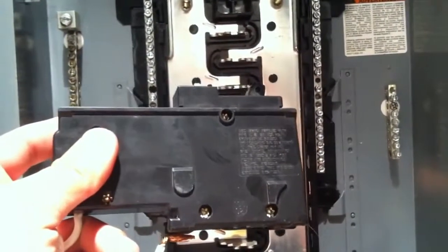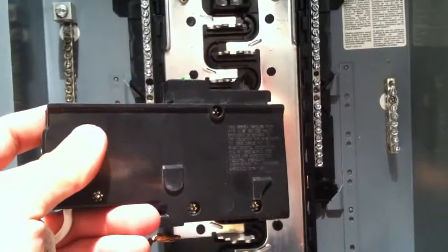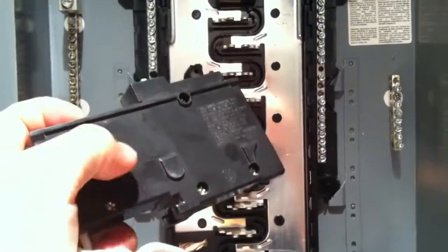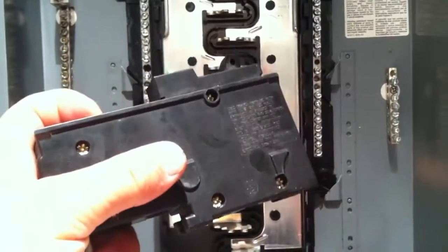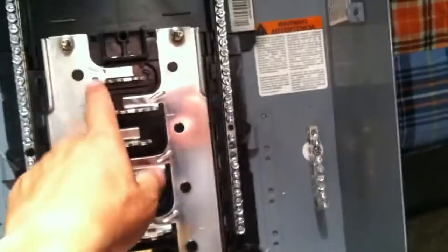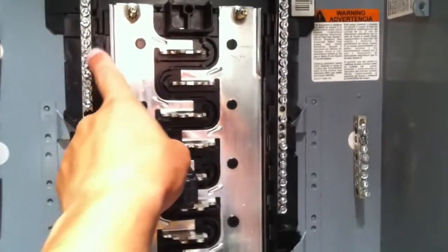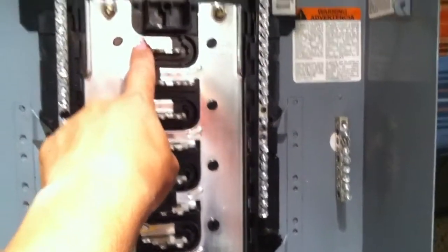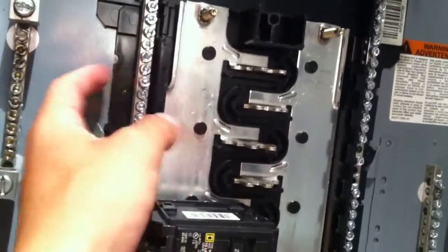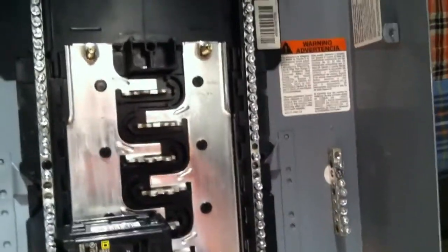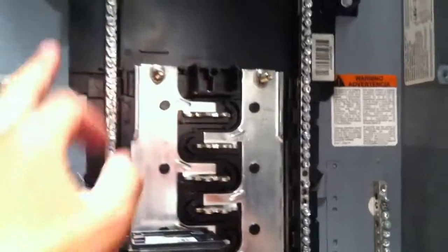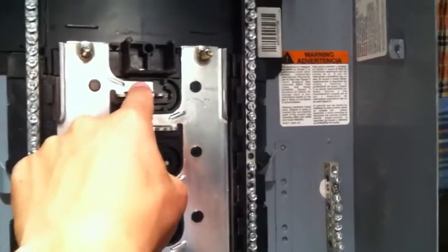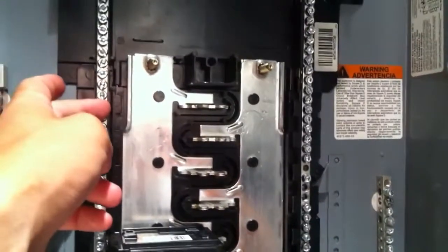So basically, to explain how these work in a little bit of detail, there's actually an electronic circuit in here. What it does is it monitors how much current is coming in from the hot line. Let's just say there's 15 amps coming in. It also monitors how much is going back into the neutral line. Typically they should be the same. You have 15 amps going through your breaker, you're going to have 15 amps going back into your neutral line. It has to be exactly the same. Normally what comes in goes right back into your neutral line, right?